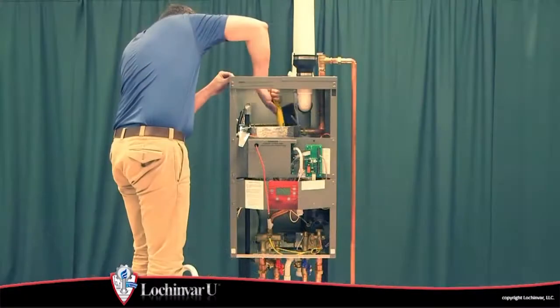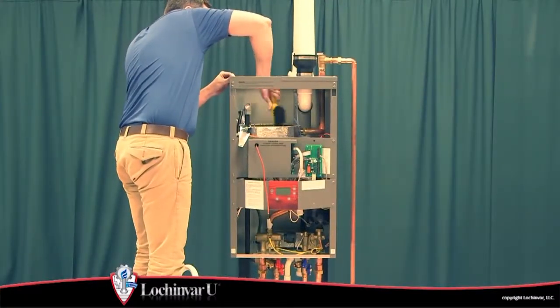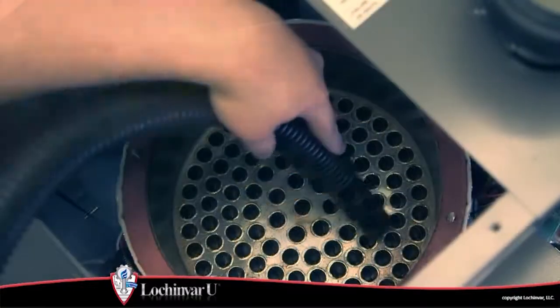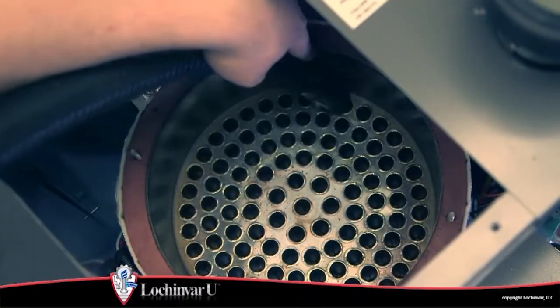Then brush the heat exchanger surface, flue tube entry points, and the combustion chamber wall using a nylon bristle brush, and re-vacuum the heat exchanger to remove debris.